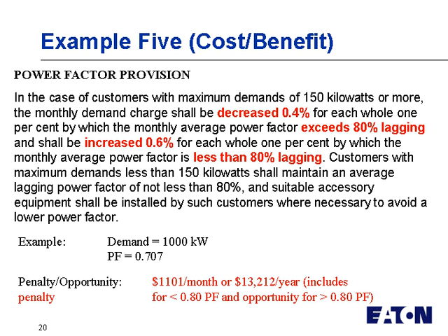This is a kind of interesting one, and I think that in many cases, again, this is one of the ones that you have to look at in a little more detail, because there's a cost and a benefit for applying power factor correction in this case. They say that they'll decrease your demand for every percent that the monthly average power factor exceeds 80%. So if you're above 80%, it's a benefit.